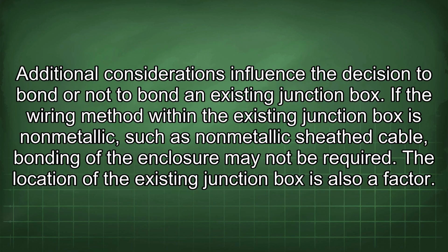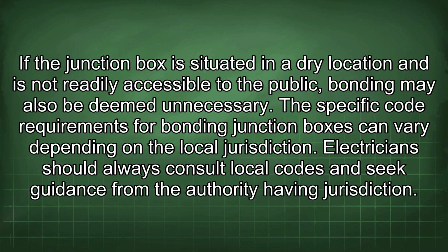Additional considerations influence the decision to bond or not to bond an existing junction box. If the wiring method within the existing junction box is non-metallic, such as non-metallic sheathed cable, bonding of the enclosure may not be required. The location of the existing junction box is also a factor. If the junction box is situated in a dry location and is not readily accessible to the public, bonding may also be deemed unnecessary. The specific code requirements for bonding junction boxes can vary depending on the local jurisdiction.